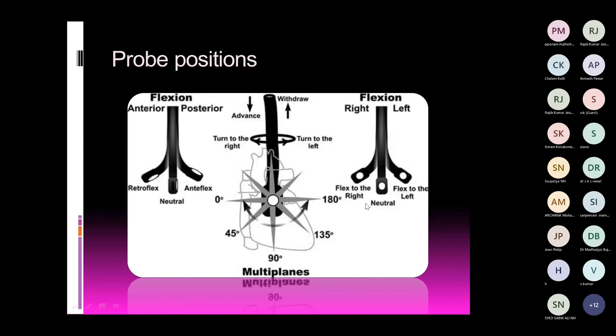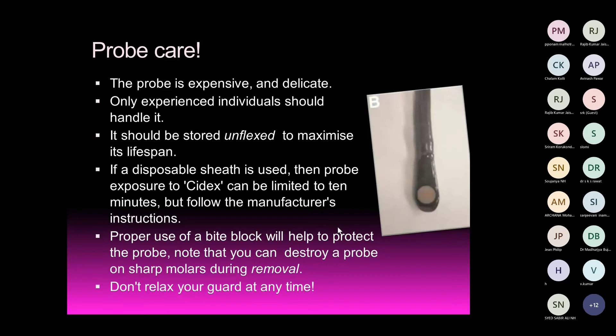Now, if you are dealing with a delicate instrument, then you have to take care of the probe. How are you going to take care of it? The probe is very expensive and delicate. Only experienced individuals should handle it, so learning and training are very important. It should be stored in an unflexed position to maximize its lifespan. If a disposable sheath is used, then probe exposure to Cidex can be limited to 10 minutes, but follow the manufacturer's instructions for taking care of the probe. Proper use of a bite block will help to protect the probe. Note that you can destroy a probe on a sharp molar during removal, so you have to be very careful when taking out the probe. Don't relax your guard at any time.